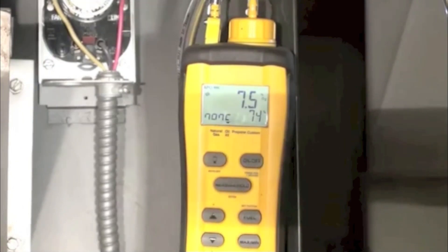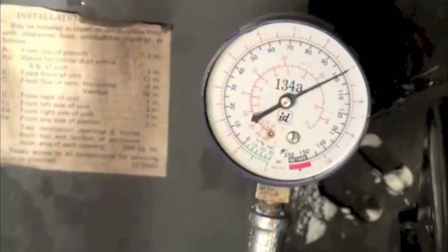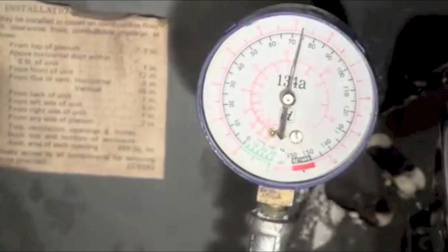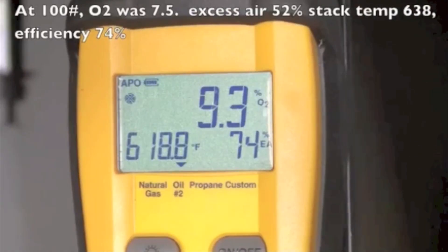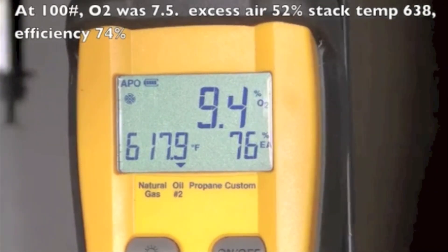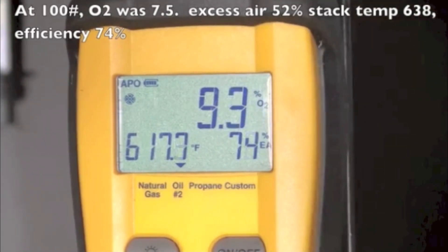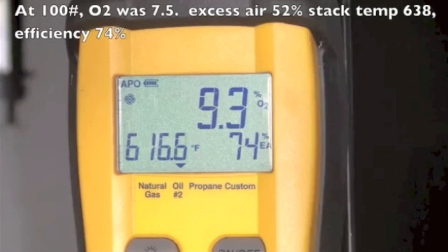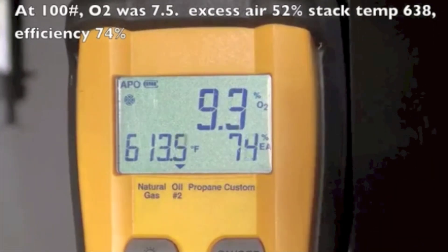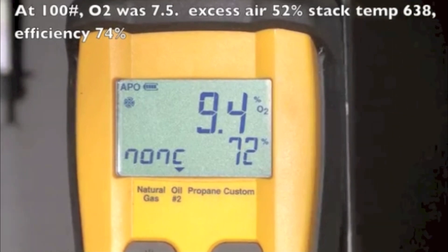The first thing we did was try lowering the pump pressure. Lowering the pump pressure is generally going to reduce efficiency, but let's see what it did. We knocked the pressure down to 75 pounds. The numbers we got were 9.3 O2, 617 stack temperature, 74% excess air — really high. After cleaning up the burn, we ended up with 72% efficiency, which went down 2%.